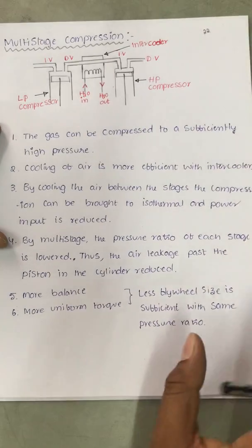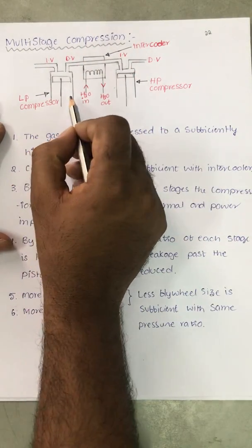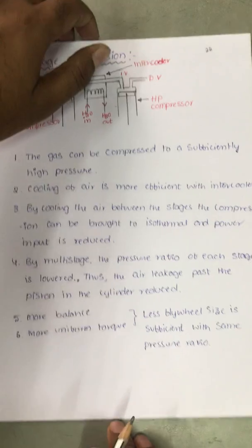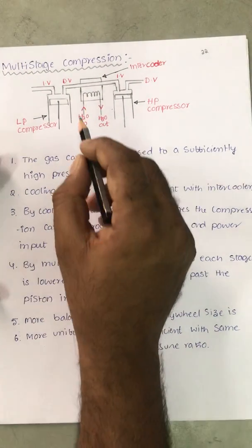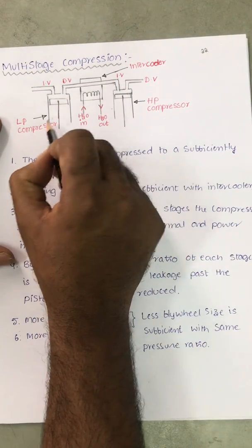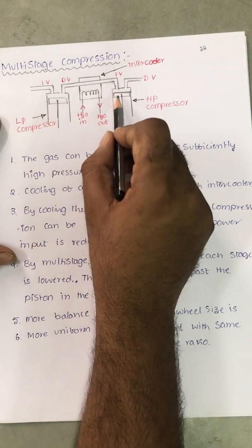In multistage compression, air is compressed in two or more stages — typically two stages, sometimes three. There is an LP (low pressure) compressor and an HP (high pressure) compressor, each with inlet and delivery valves. The inlet valve of the HP compressor is connected to the delivery valve of the LP compressor. After primary compression in the LP compressor, the air is sent to the HP compressor for further compression.